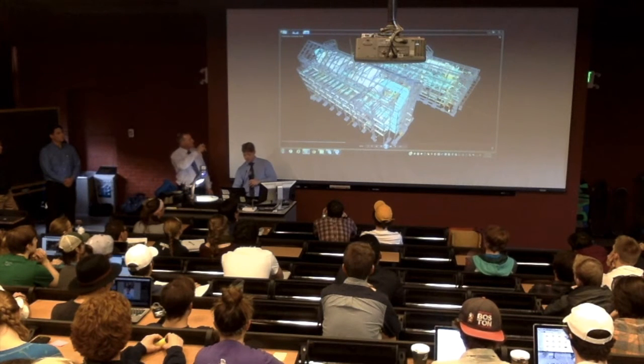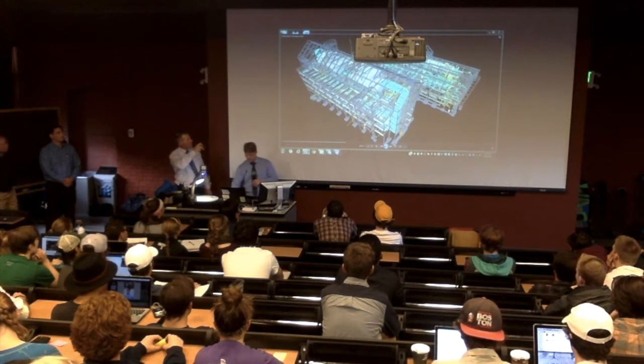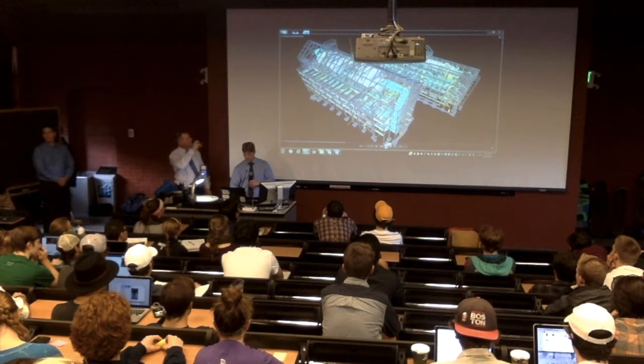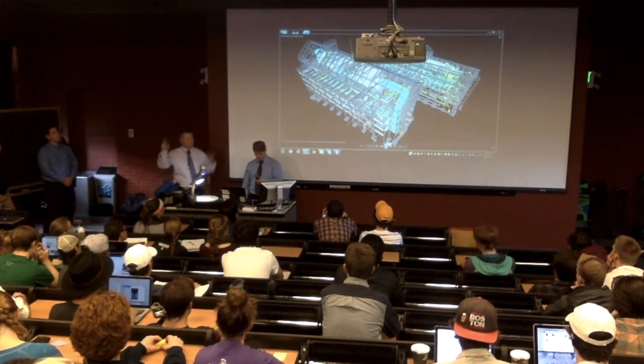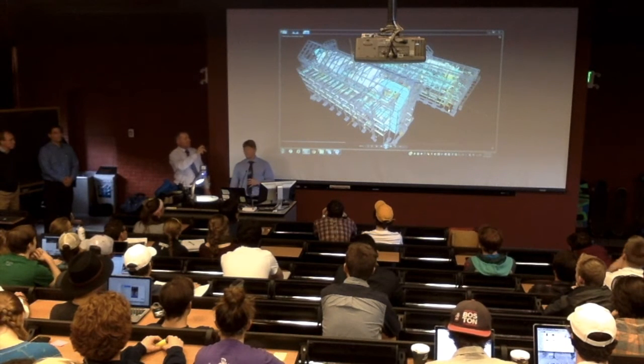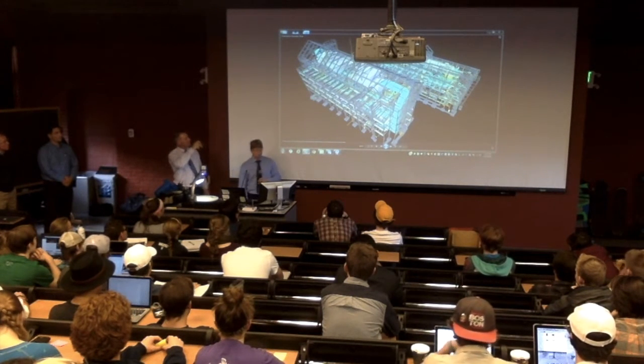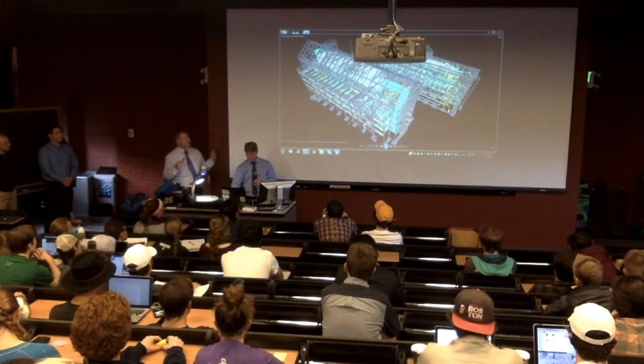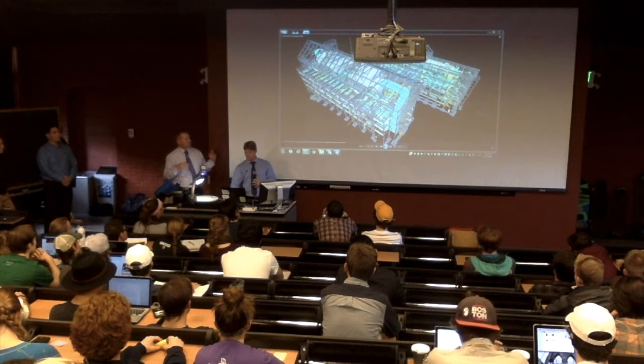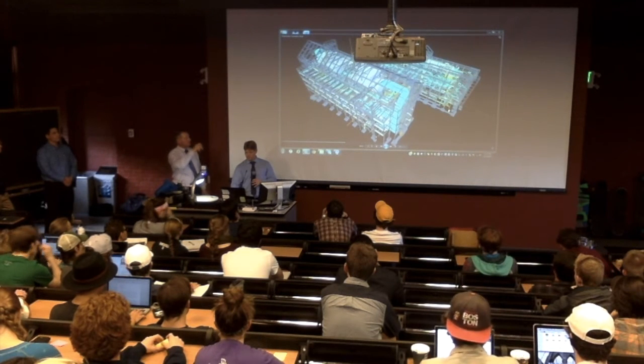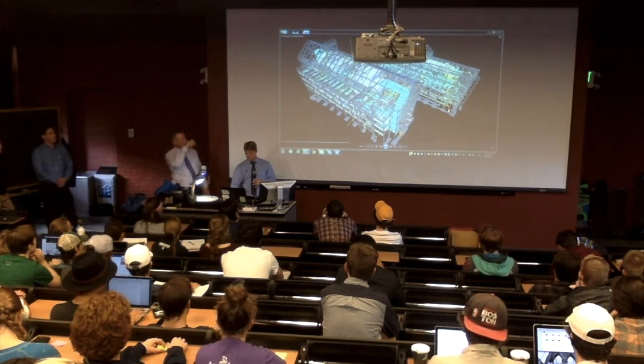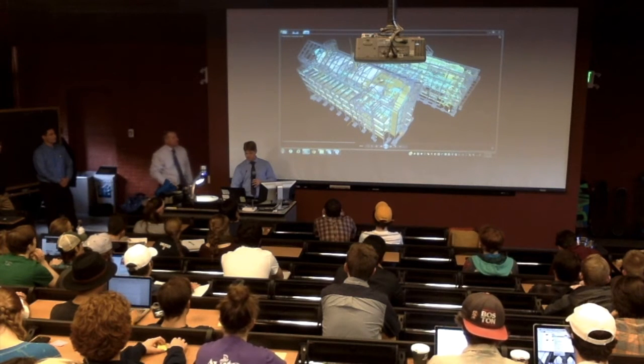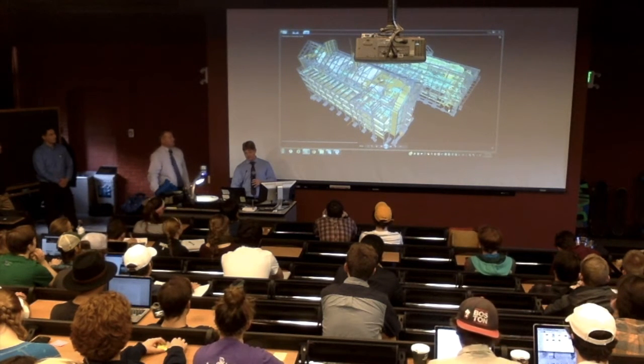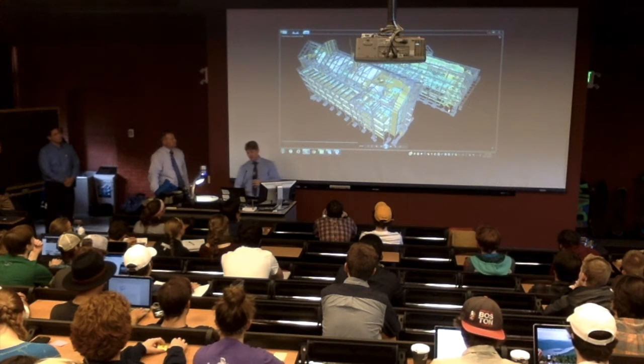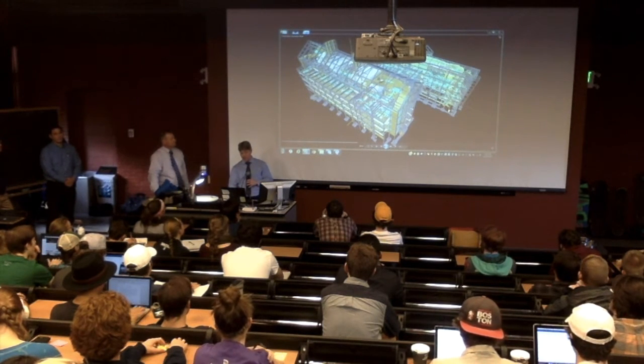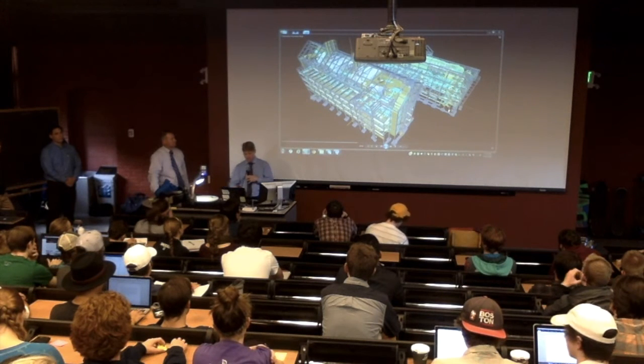So these are the air handling equipment that we're talking about. Supply air units with large ducts that come down through the building. Exhaust stacks. So when you go outside, you can look at the building. This is in the mechanical penthouse up here. And it took a lot of effort to design the penthouse to fit within the structure, and then the shafts that come down through the building. We'll talk a little bit about designing these individual components. So that was just the supply system that was overlaid first, and then you put the exhaust on top of that, and you see the major shafts that Alan's talking about that go down and feed each floor from north and south.